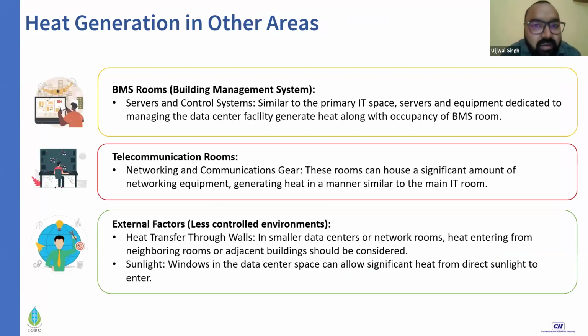Now I've given the headline here: heat generation in other areas. Why other areas? Because normally BMS rooms and lobbies and other areas, data center design doesn't recommend using chillers for these, and they keep chillers secluded for the IT space and UPS room. Other areas normally use VRF or other standalone cooling devices, so the overall chiller circuit remains primarily for the core areas only.